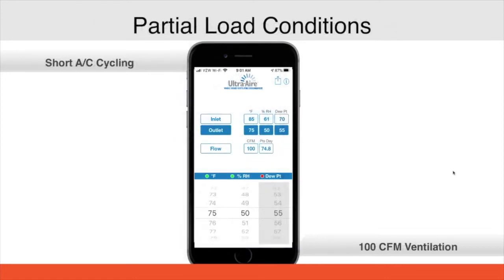So what happens when we get into our partial load conditions? So we have 85 degrees, 61% RH, 70-degree dew point outside. There's my indoor design conditions that I want. I still have my 100 CFM of outdoor air, and I'm going to need 74 pints of water removal a day. So I've got to figure out if my AC system is not running, how am I going to get that water removal?